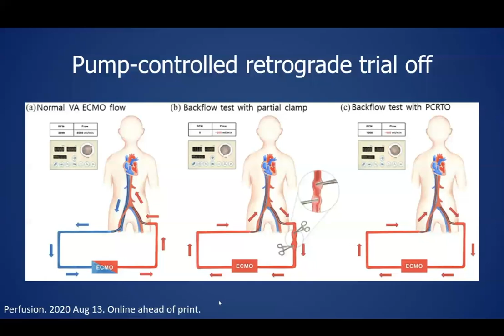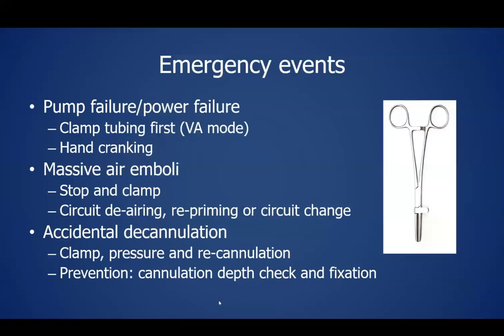The tubing clamps should be available at bedside all the time for circuit-related emergencies. If the pump stops spinning in VA mode, retrograde exsanguination can lead the patient to cardiac arrest within minutes, so the clamp should be applied to the circuit until the troubleshooting has been done.